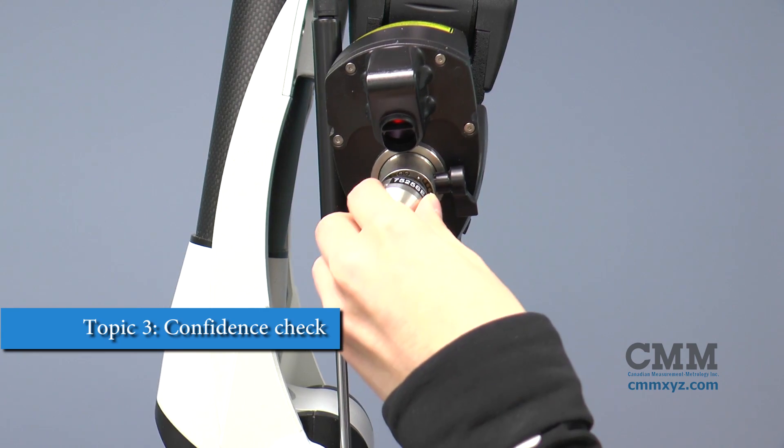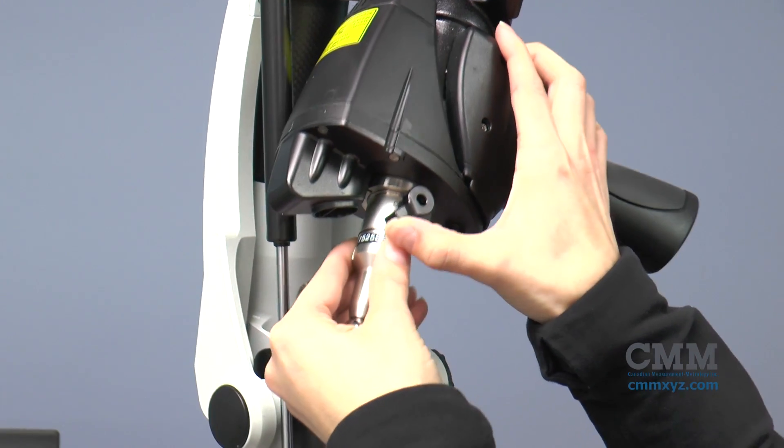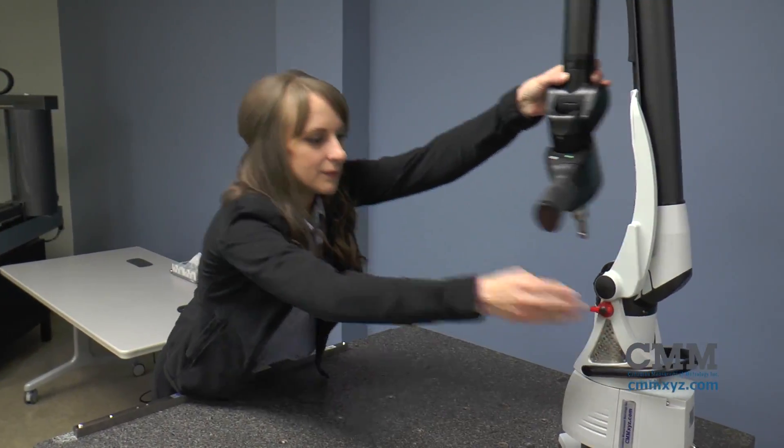Topic 3: confidence check with your ROMER system. The following checks will allow you to check your arm's accuracy. Length check — what is a length check? This is used to test or calculate the accuracy of the arm inside a given volume.